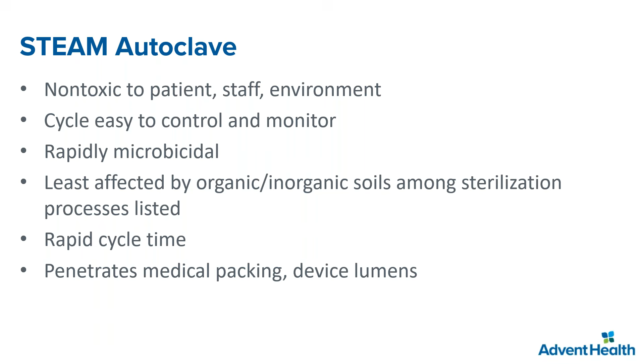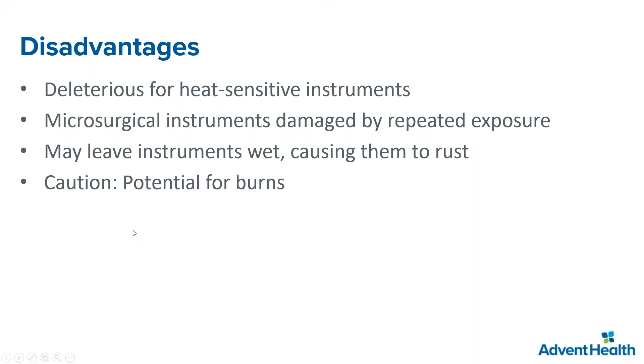What are the disadvantages? Heat-sensitive instruments cannot be processed in a steam sterilizer because you are going to melt those devices. Microsurgical instruments are damaged by repeated exposure and may leave instruments wet, causing them to rust. And if the item is wet when it comes from the sterilizer, it means that the sterilizer needs to be shut down and checked to see what is happening, and those instruments cannot be used. And also, since this is steam, at 275 degrees the potential for burns is very high, and believe me, it's a very bad burn.